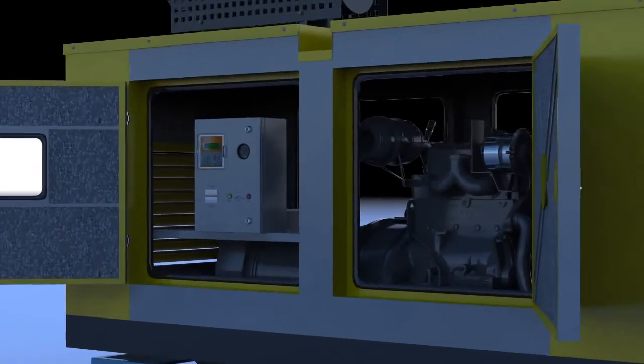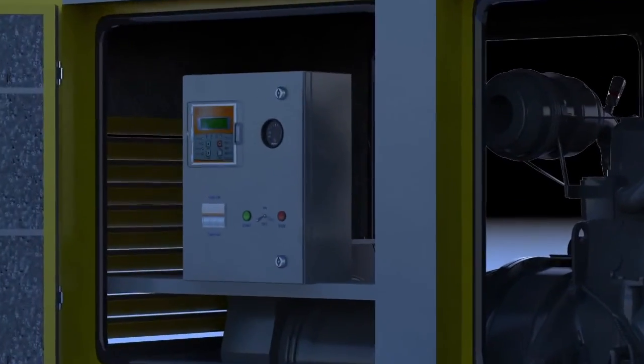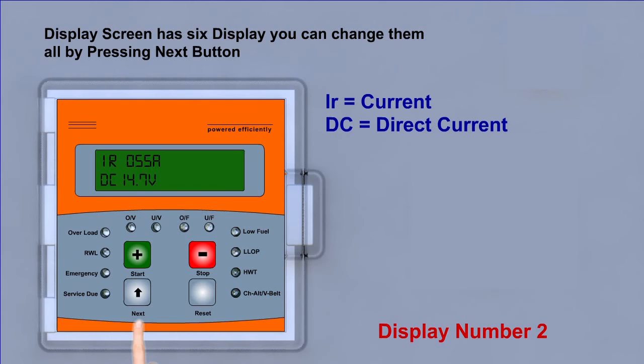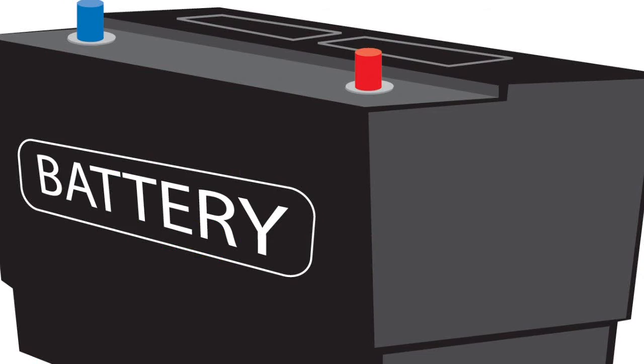Check the direct current. In display menu number 2, direct current should be minimum 12 volts. If it is less than 12 volts, then battery is required to be changed.